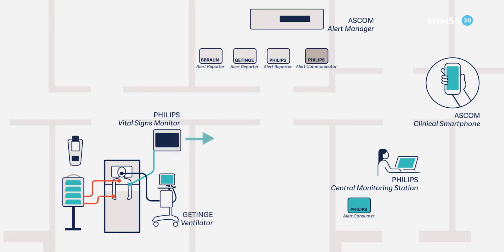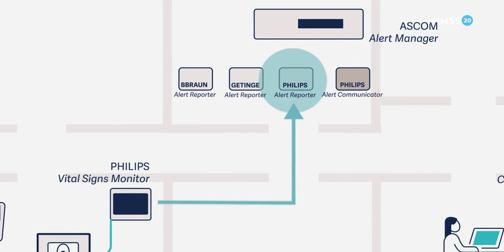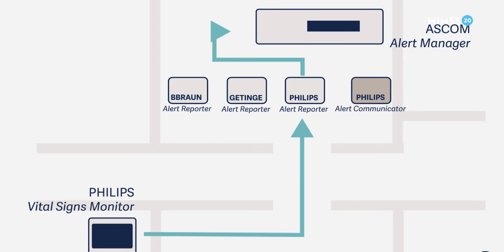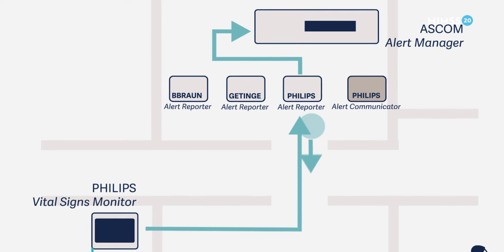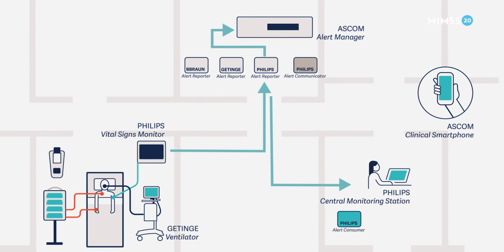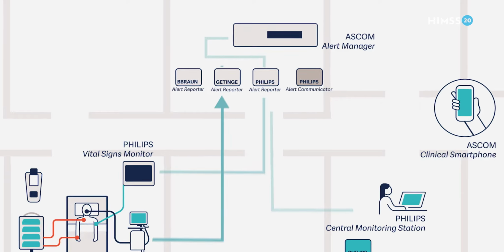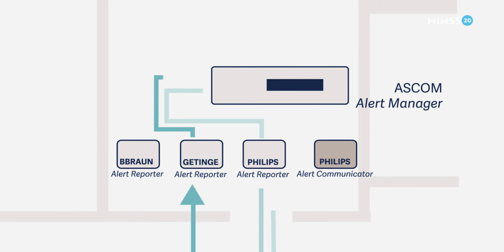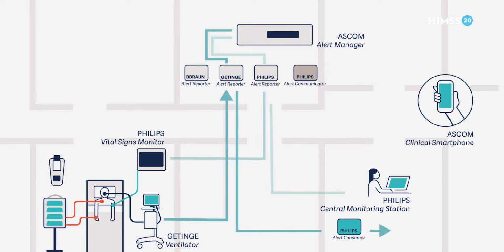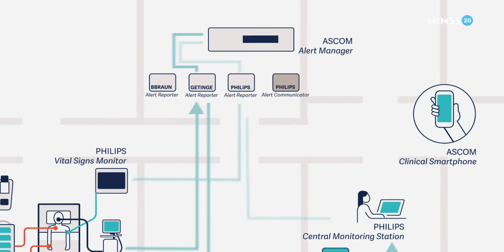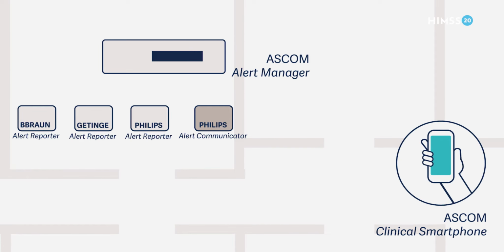An alarm from the Philips vital signs monitor occurs. The device is in quiet mode, so there is no audible noise. The Philips Alert Reporter sends an alert report message to the ASCOM Alert Manager and to the Philips Central Monitoring Station. An alert report message is also sent from the Getinge Servo-U ventilator, which is in quiet family view. The alarm goes via the alert reporter to the ASCOM Alert Manager and to the Philips Central Monitoring Station via its alert consumer. The Alert Manager decides where to route the alarms.